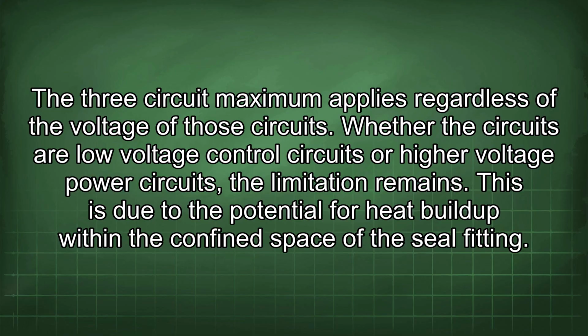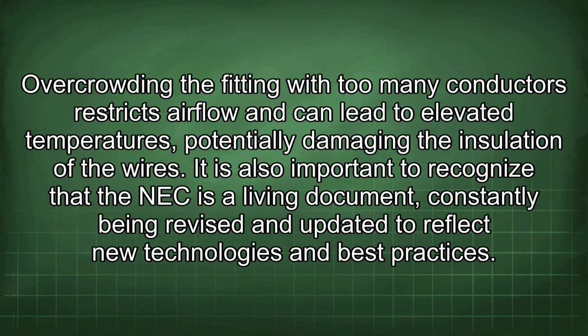Whether the circuits are low voltage control circuits or higher voltage power circuits, the limitation remains. This is due to the potential for heat buildup within the confined space of the seal fitting. Overcrowding the fitting with too many conductors restricts airflow and can lead to elevated temperatures, potentially damaging the insulation of the wires.